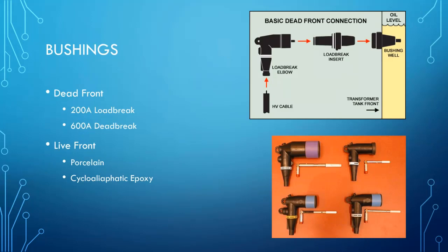There are many types of bushings in a transformer. You can order live front bushings, which I really do not recommend. There are dead front bushings that are 200 amp, or they come in a 200 amp form factor or a 600 amp. The 600 amp is a non-load break device. It's a threaded connection, so the transformer must be de-energized in order to pull that device.